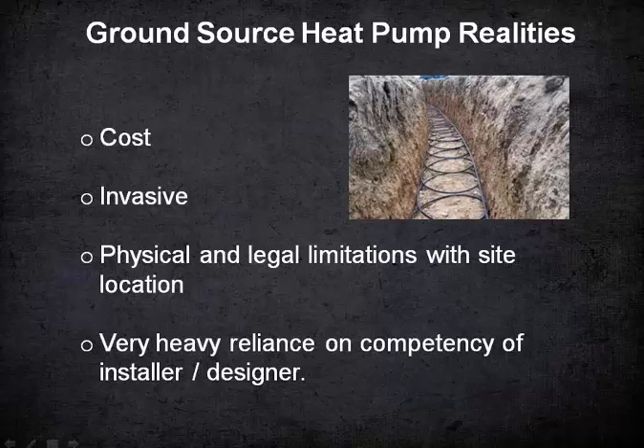And I'm old enough to remember the days of a 600-foot ground loop being standard, even as short as 400 feet of pipe made into a slinky, and those systems didn't work too well when it got to be January in South Dakota. So then the system kind of went to 600. It's pretty much standardized now at 700 feet per ton with a slinky type design, and we've got numerous people from Wyoming to the Dakotas and Nebraska that are doing it with 800 feet. The old rule of thumb was to add an extra loop. Rather than adding that extra loop now, they'll put 800 feet of pipe in per ton, and they work fine.